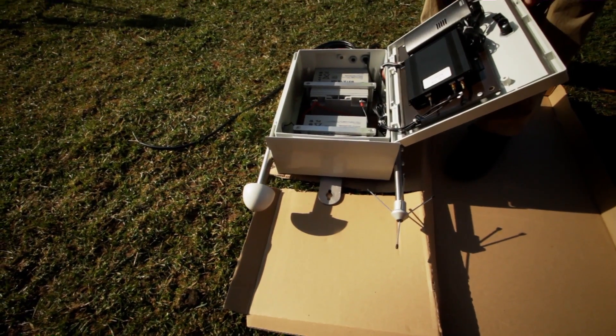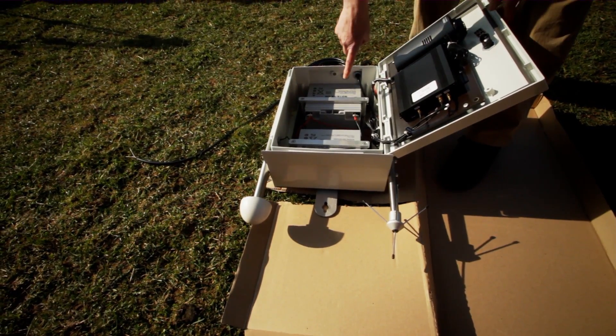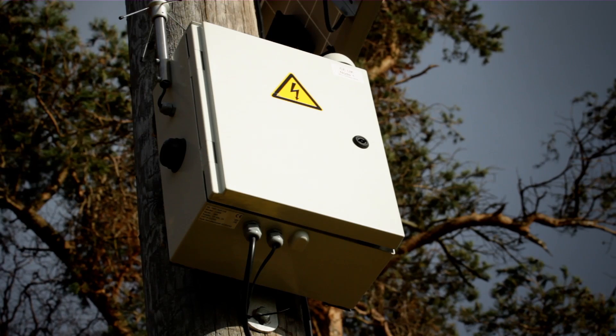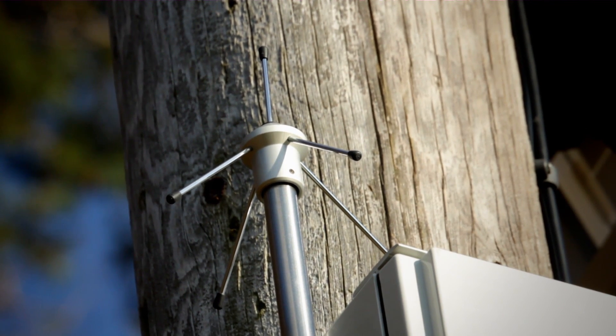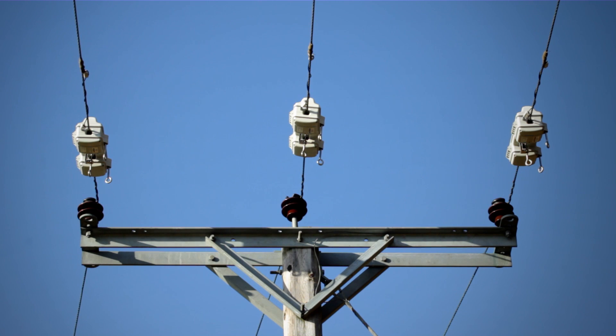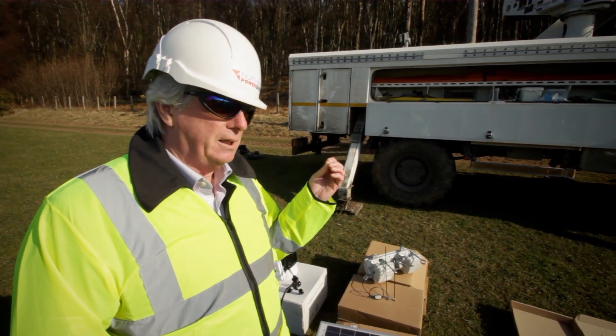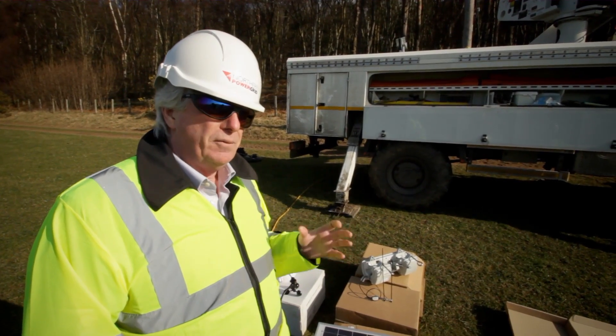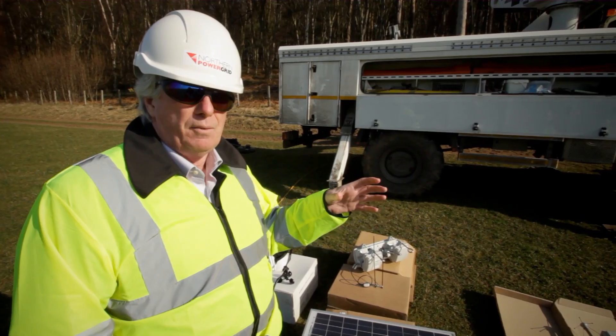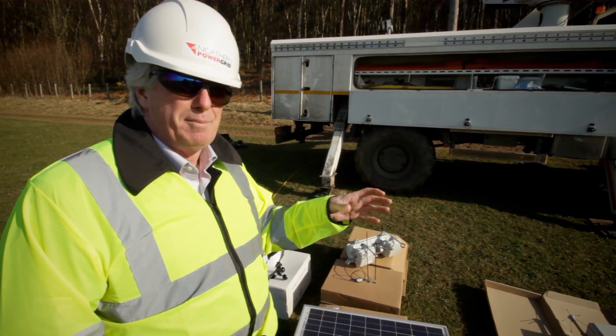This is the controller, made up of an SNG — a sensor network gateway — and this is the device that captures the information via radio from the power line sensors and forwards it by GPRS back to the server. The data from Northern Ireland has proven to be useful, and it's a tried and tested device that seems to be functioning admirably. Every five minutes there will be reports sent back to a server with data from the power line sensors: the surface temperature of the conductor, the current flowing in the conductor, and all the weather parameters. All of those parameters are then analysed by the other teams in the project to assess the best approach for dynamically rating this type of circuit.